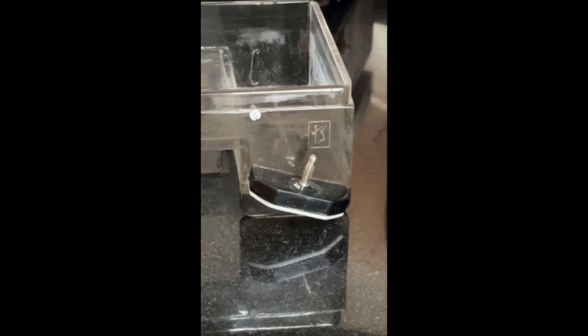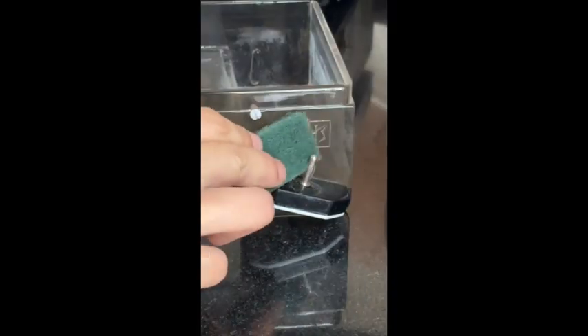Cause number 7. Oxidation or deposit formation on the contact terminals of the electrophoresis apparatus. Disconnect the instrument. Clean the terminals using a slightly abrasive material. Reconnect the instrument and try again.